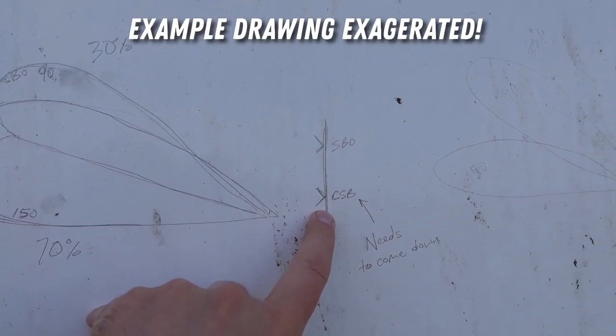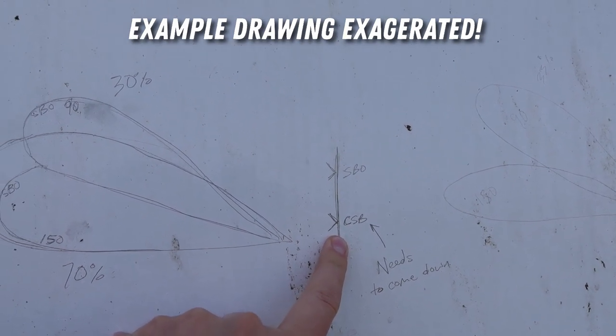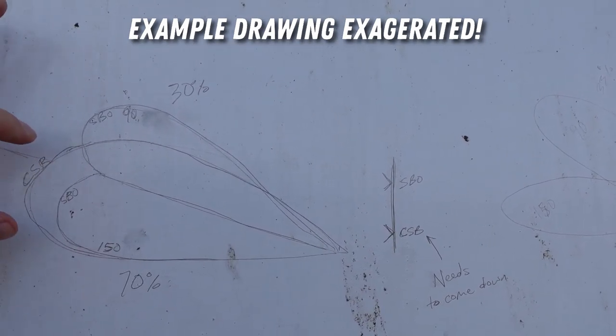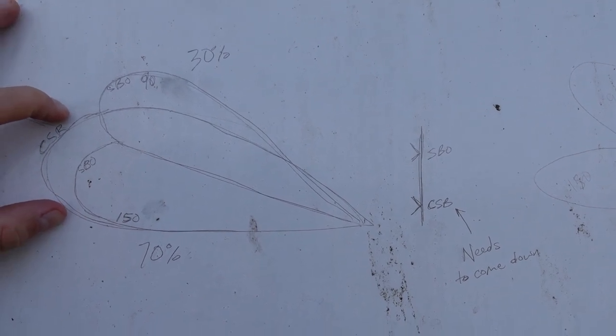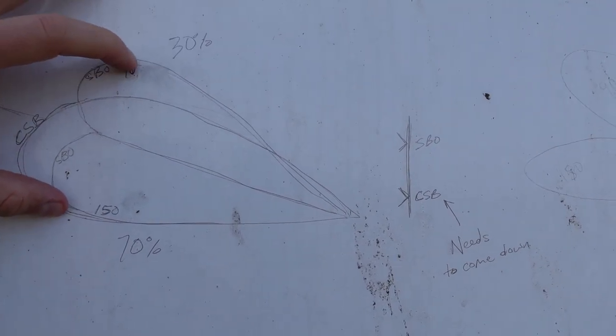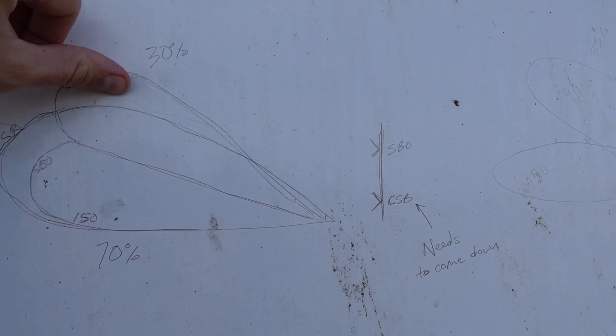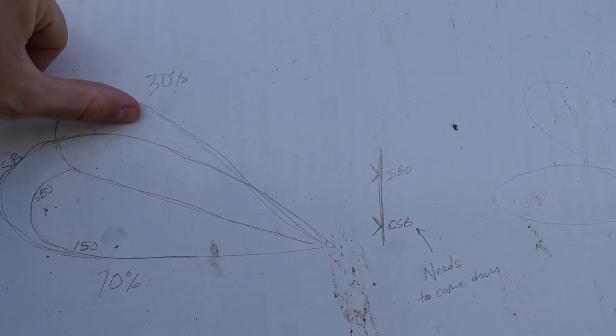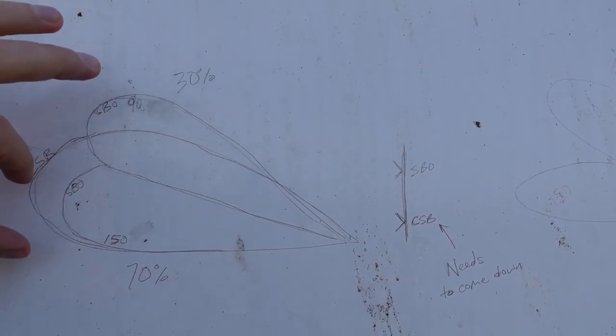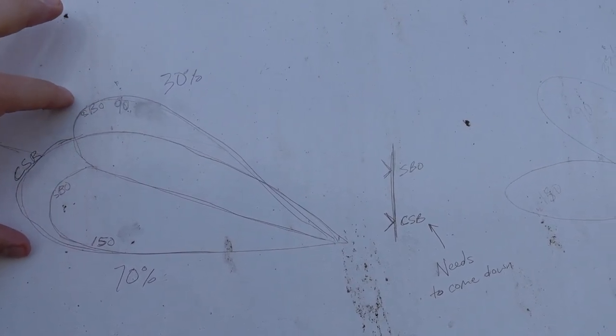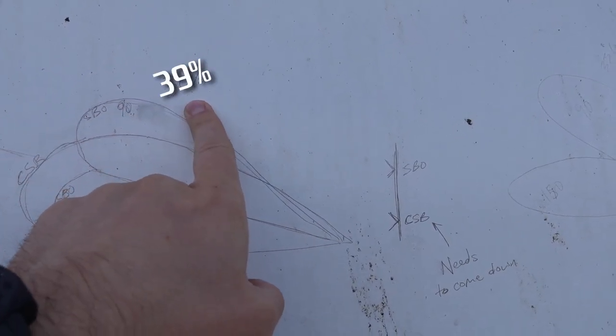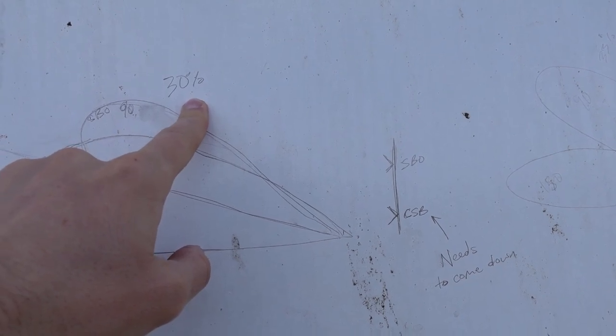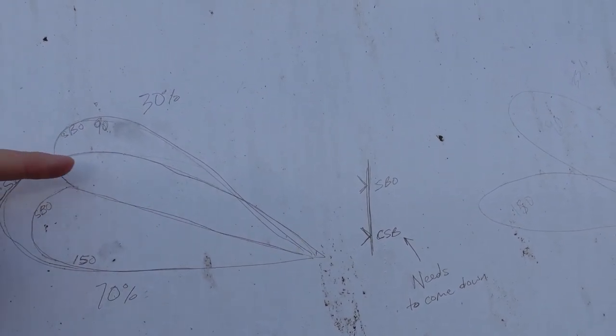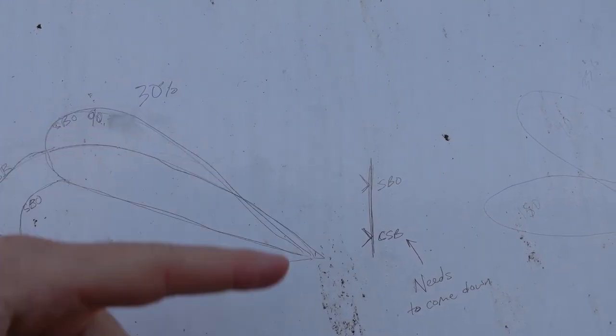The lower antenna is probably too high and needs to come down, because the CSB lobe seems to be too low relative to the SBO lobe. So we're losing some of that SBO signal — it's not overlapping equally on the CSB main lobe. That's why we're reporting to 30%. And that's what flight check reports: the symmetry, or the amount of 90 hertz lobe.